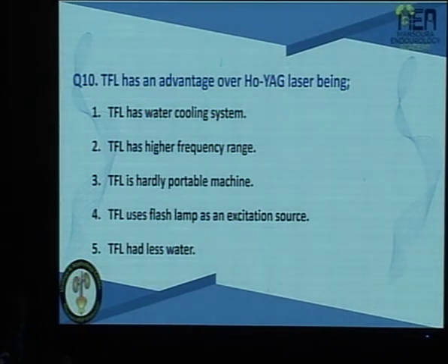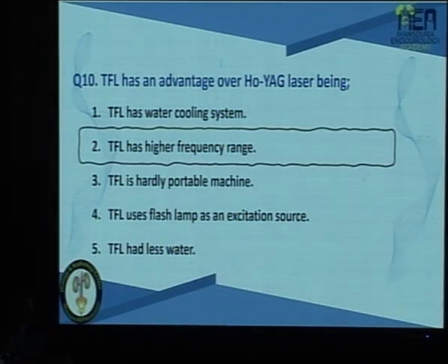I think the last one correlates to the first question. I told you that it has 4 times greater absorption coefficient compared to the holmium. So the last one is incorrect. It uses a flash lamp as the excitation source? No, it is a diode pumped laser; the diode is the excitation source. It's hardly portable? No, it's quite smaller. It's a portable machine, much smaller in weight and size. Has a water cooling system? No, the cooling system is just a fan. So it has, of course, a higher range of frequency that can reach up to 2000 hertz.